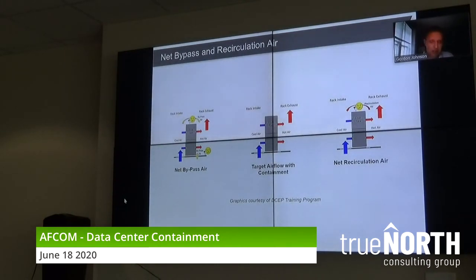You have a heat load. The air, some of it's going into your servers, a lot of it's bypassing. It's going through openings in the racks, it's going over the racks, and it's returning back to the CRAC returns as cold air, so the CRACs aren't running as efficiently as possible, and you're basically wasting air. Think of bypass air. It costs money to cool the air, it costs money to blow the air, so you're wasting money.